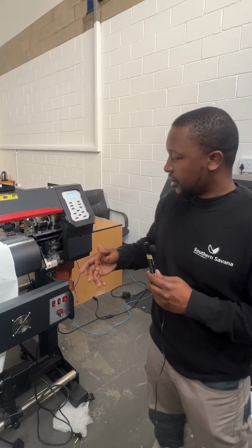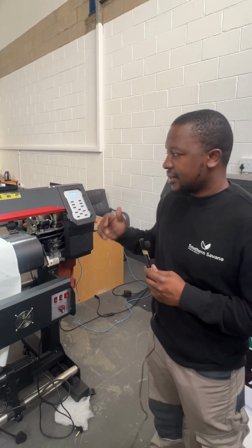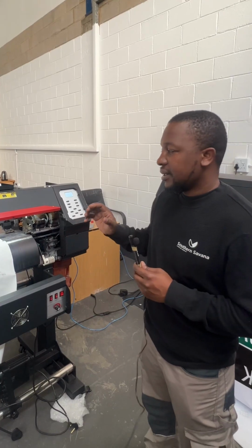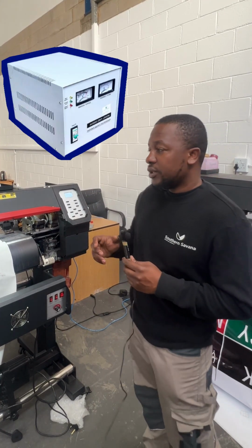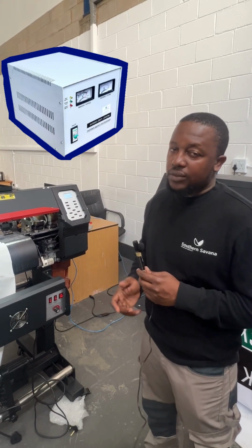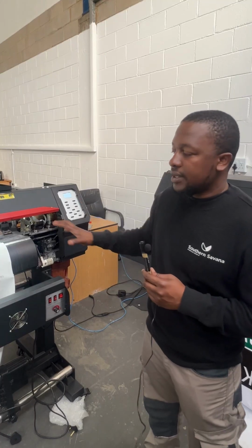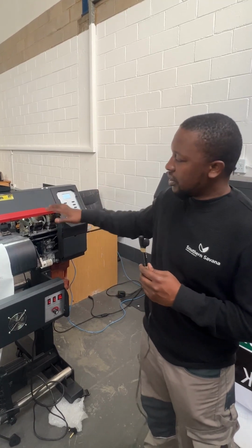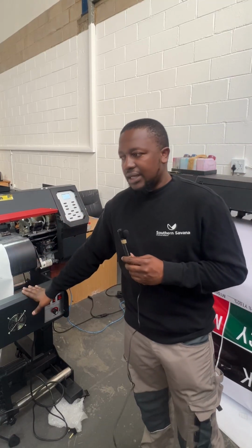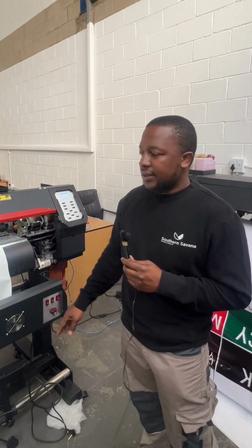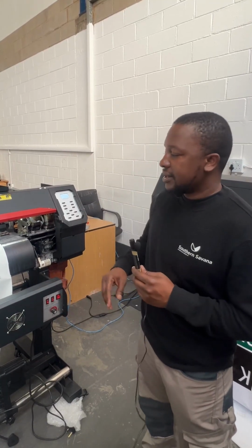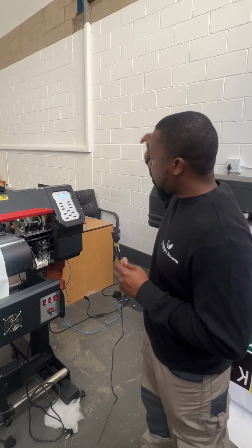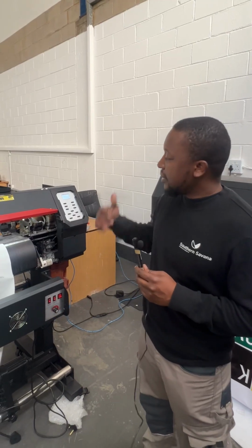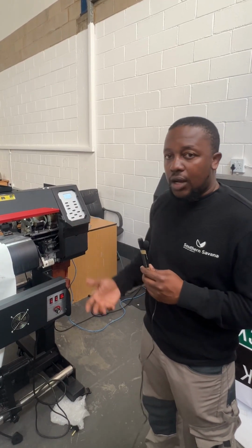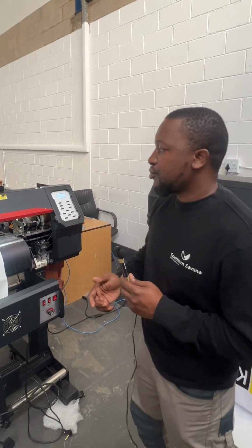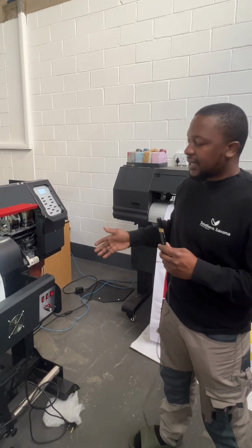So for the future, we usually recommend that clients install these machines together with a voltage stabilizer. And we usually recommend a 3 kVA voltage stabilizer, which works well for these machines. So you only need to plug the machine into the regulator, and probably have an independent plug for your heaters. The heaters don't need to run through the stabilizer. So the connection is very simple. Your Eskom power goes into the stabilizer, and then the machine is plugged into the stabilizer output point. So you're basically just running the machine with the stabilizer in between.